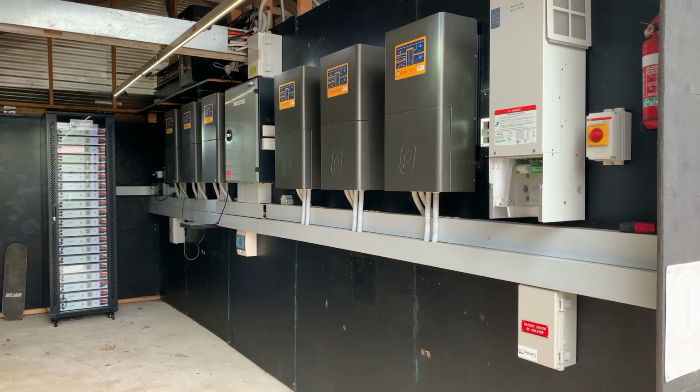But the purpose there is to have both DC coupled charging and AC coupled charging. One of the reasons for doing this, I'm going a little bit early on the tech here, is that in a pure AC coupled environment, you're very reliant on the microgrid battery system keeping the inverters on. If the inverters shut down for any reason, the whole microgrid shuts down, and you can't even charge from any AC coupled sources because they all require a stable grid to connect to. So having some DC coupled charging is kind of a safety belt, really, that you can always charge that battery from the sun, and therefore that will bring the battery inverters back to life, and then the whole microgrid comes back up and magic happens.